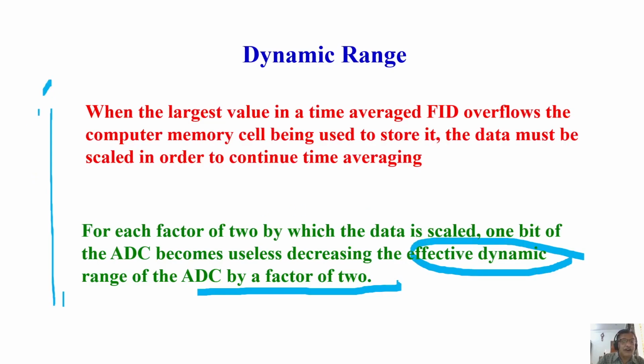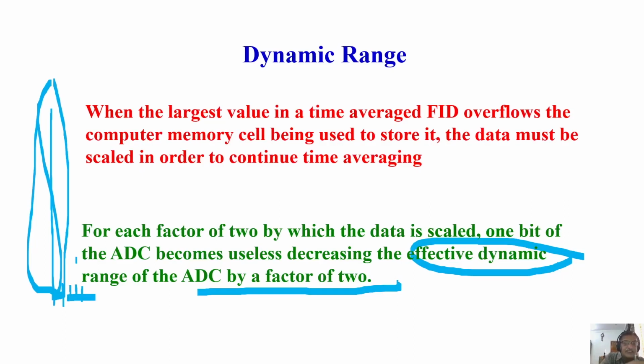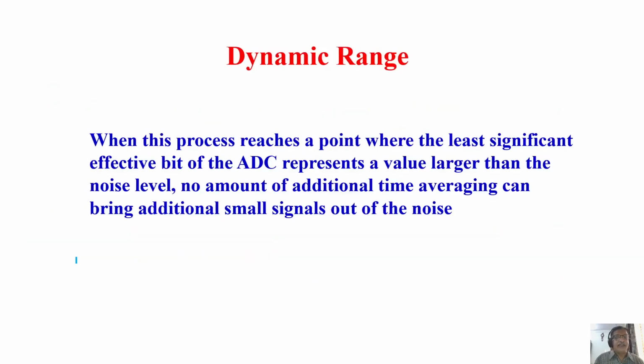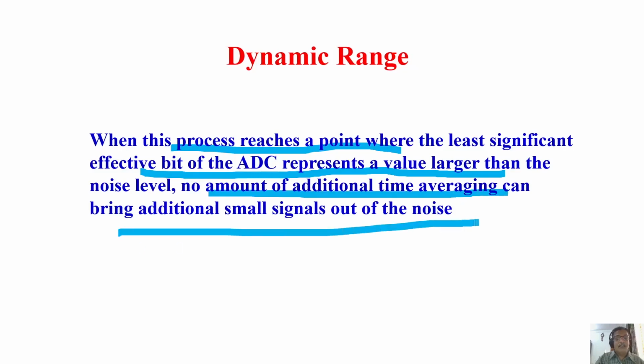So in which case, a very strong signal, if it is there, you have a dynamic range problem. Weak peaks sometimes you will not be able to see, because the memory overflow cuts the signal, scales each of the signal by 2. As a consequence, weak signals also will get reduced. This is a dynamic range problem. Please understand, it is very important. Sometimes when you have a very strong signal, you may not see the signal from your sample. It is for this reason, because the ADC gets full. And when this process reaches a point, then what happens? ADC represents a larger value. No amount of additional time averaging can help. Small signals will never be brought out of the noise.